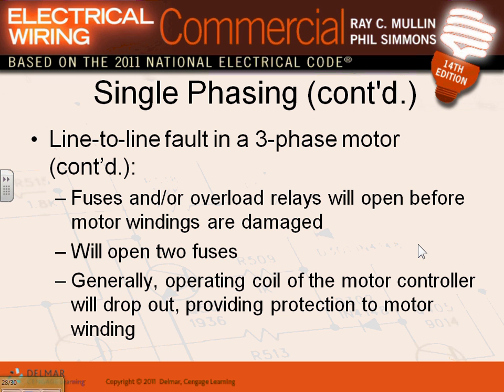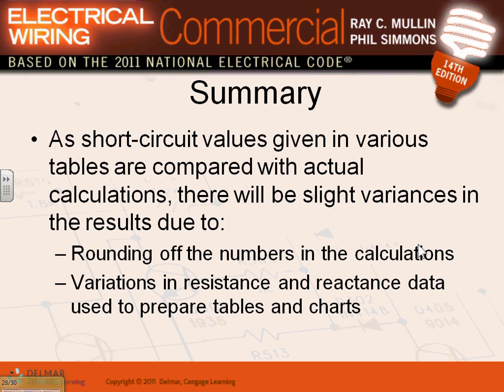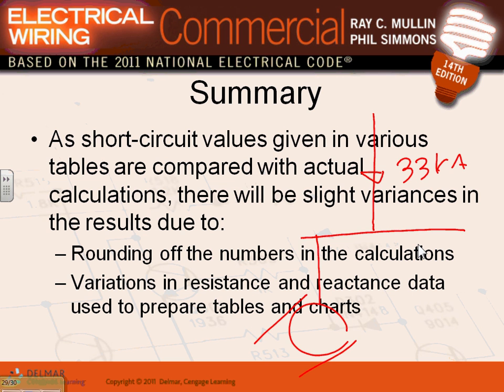Okay, the last thing I want to say, guys, is the contribution from motors. If you have motors in your system, they always contribute equivalent to the locked rotor current. Okay, so take this. Very simple, and I'm going to write this one, and then I'm going to stop. If the available short circuit right here coming in is 33 kiloamp, and I have a big air handling unit right here, and let's just say, for the ease of installation, it was 100 amp. It's in horsepower, but it's 100 amp, just for the ease of installation.